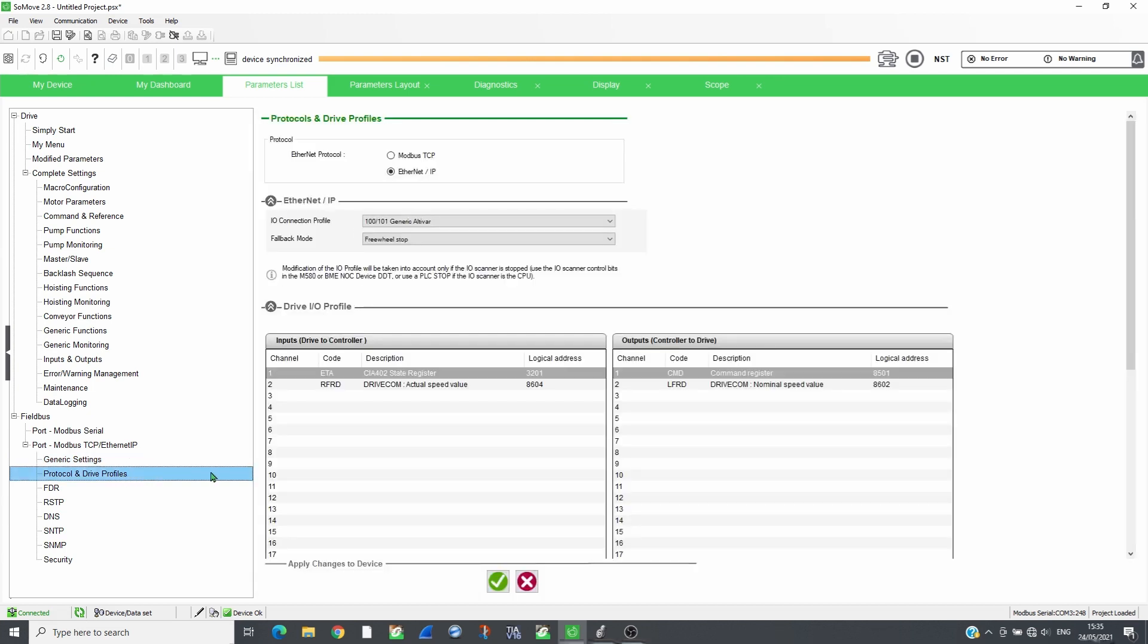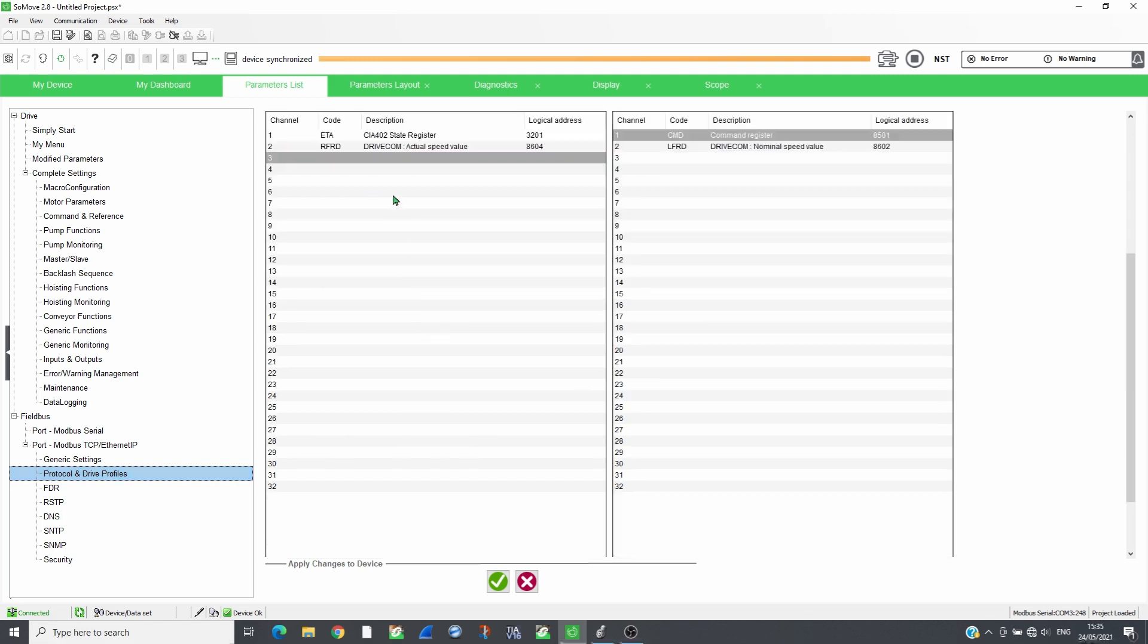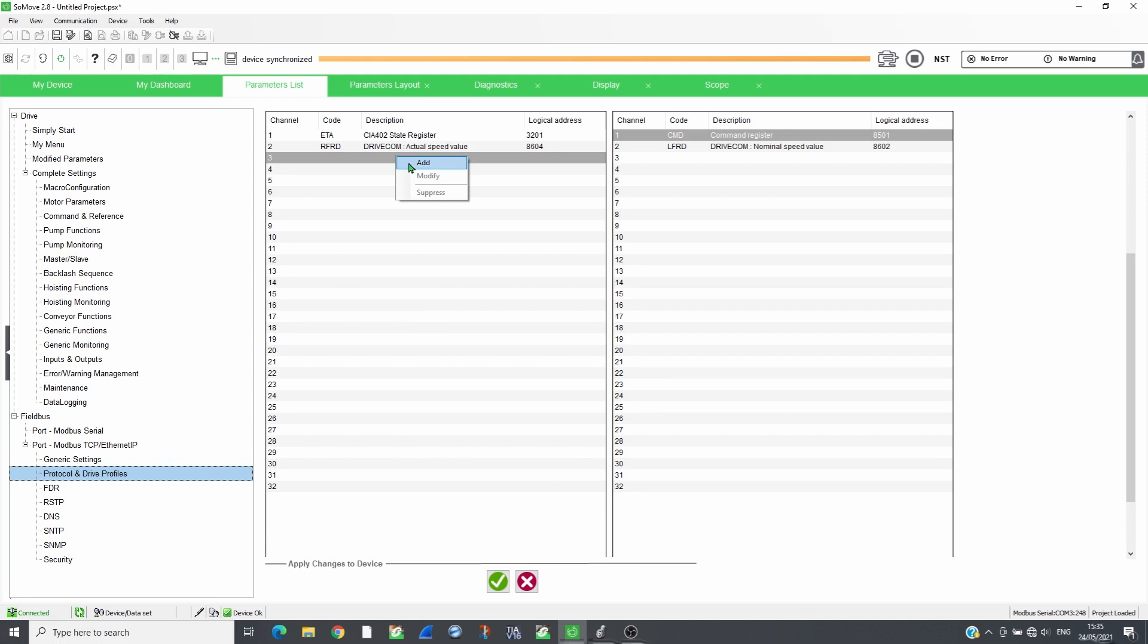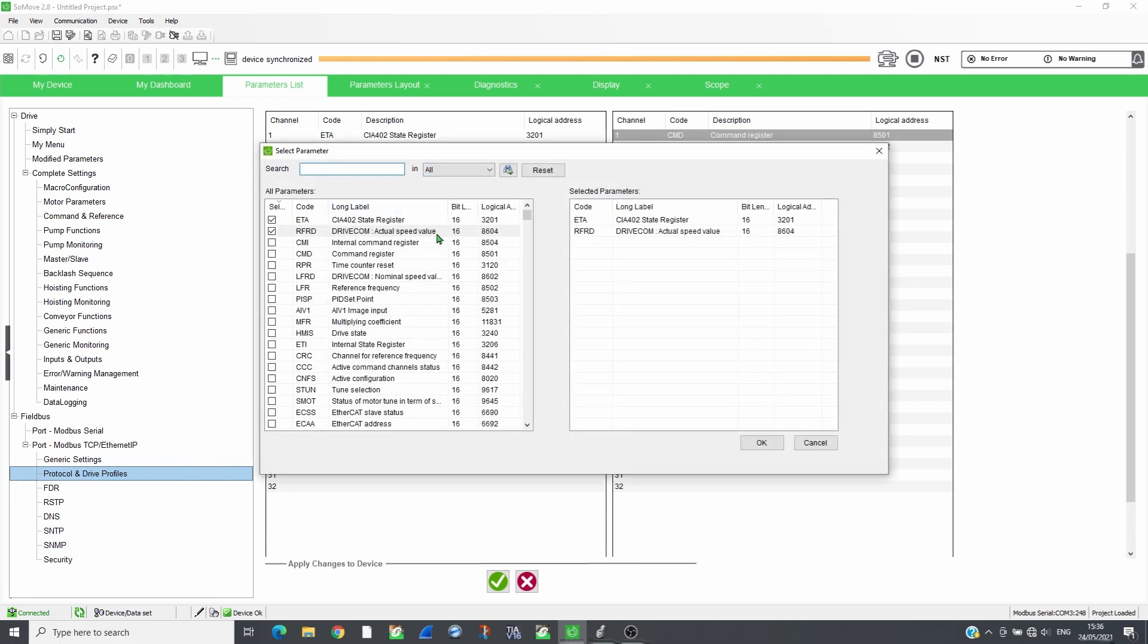Select the protocol Ethernet IP and choose the I.O. connection profile, the assembly. In this video, we will use 100, 101, 32 input and 32 output registers. Fill out the scan table with the parameters, registers, to scan.